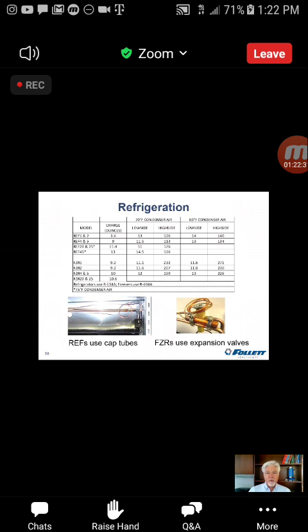Now, why would Follett do that? Remember, these are high-performance refrigerators and freezers, with rapid temperature recovery. A capillary tube knows only one speed. It is a fixed metering device, so it does not vary much based on load. It may vary slightly with changes in head pressure. That's it. That works for a refrigerator, because the load is fairly constant. What makes a freezer different? The defrost cycle. That changes everything.